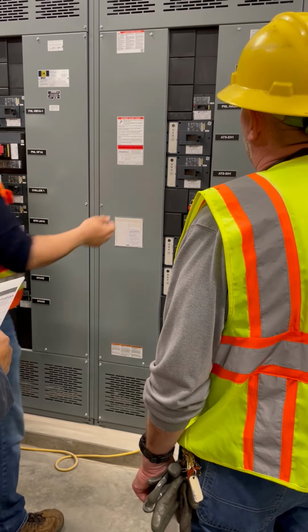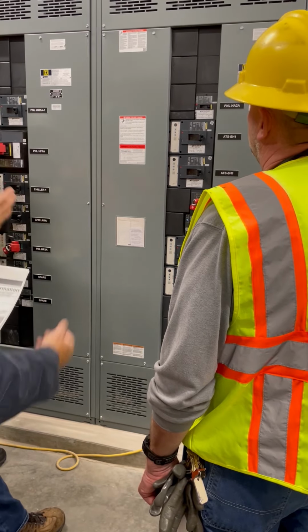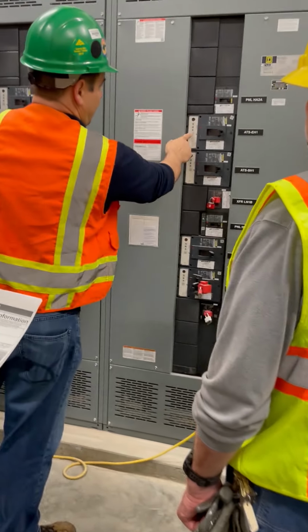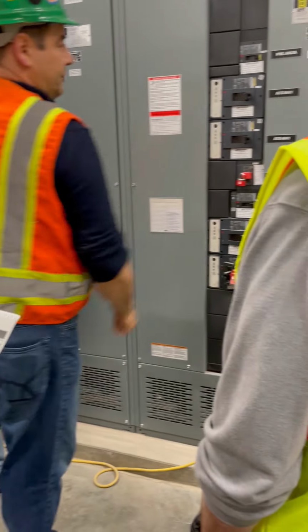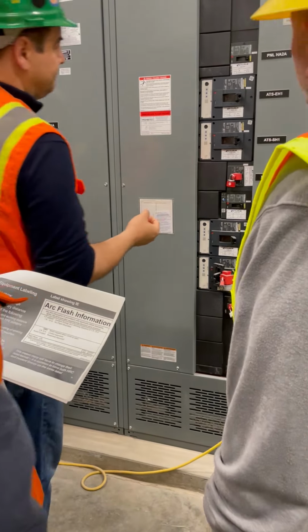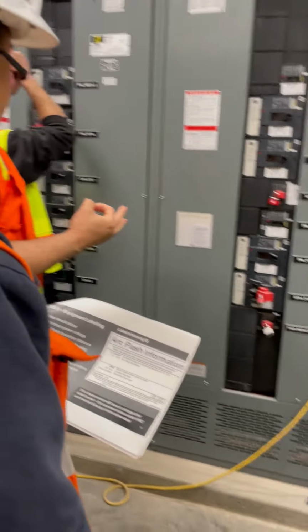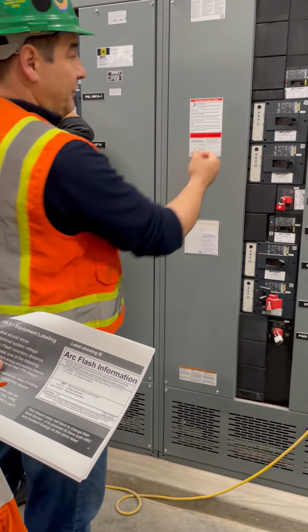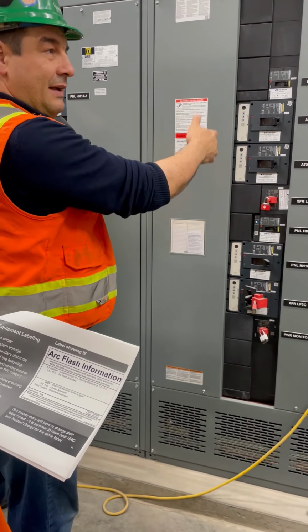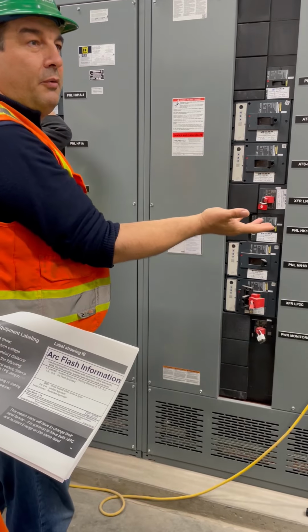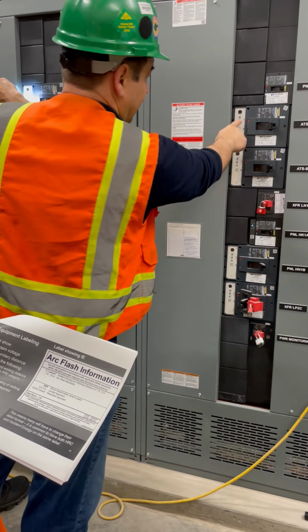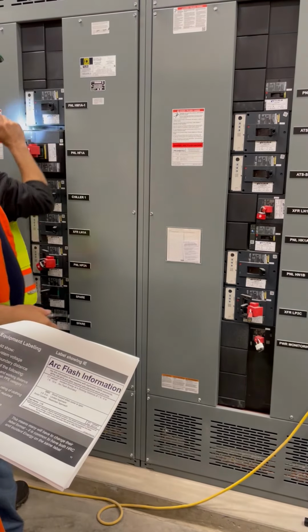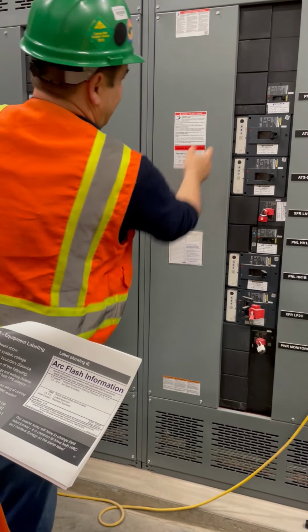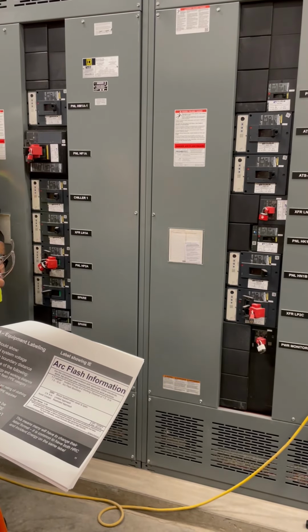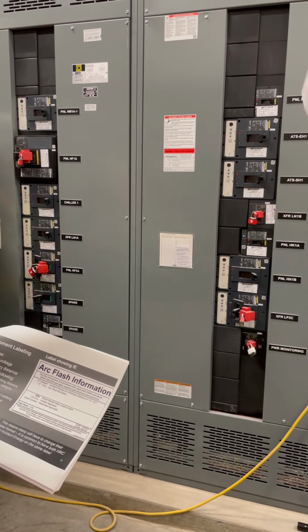Oh, wow. So this is where the settings really have to match or come into play, because otherwise, this breaker is at 400 amps, rated for 80% of the current, so you can definitely put more than 200 amps, but if you put more than 200 amps, you'll trip the breaker. And you wouldn't know why, you'd say it's a faulty breaker, when in fact those settings are very important. The rest of it, short time and instantaneous, is different, but long time is one of the most important settings.